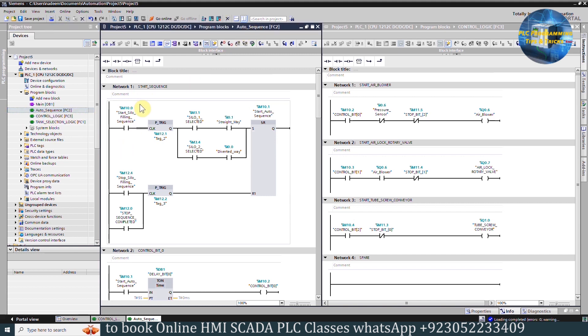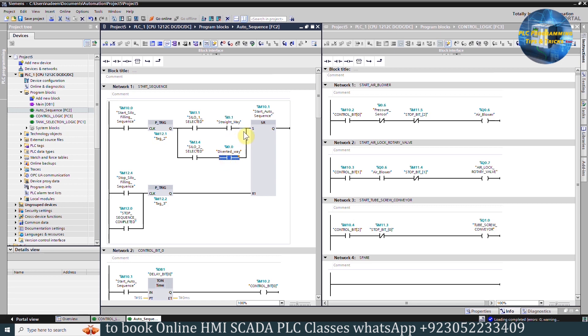In Network 1, on the rising edge of the start-filling sequence bit M10.0, if silo 1 is selected and rotary valve feedback I0.1 is on, or if silo 2 is selected and rotary valve diverted-way feedback I0.0 is on, it will set the start auto-sequence bit M10.1.